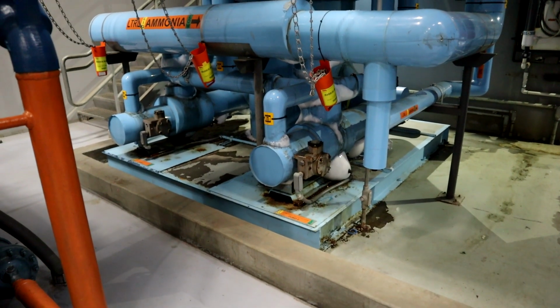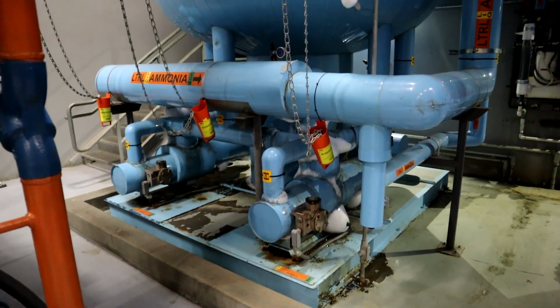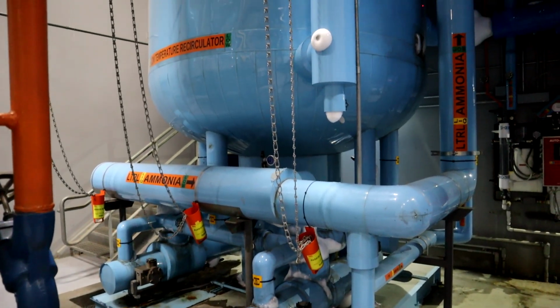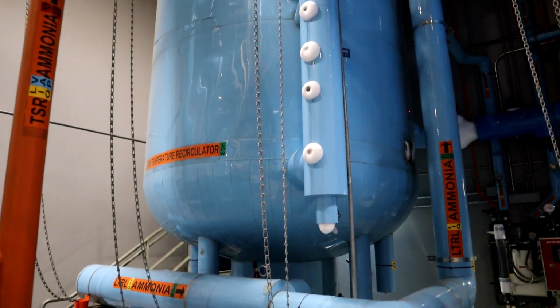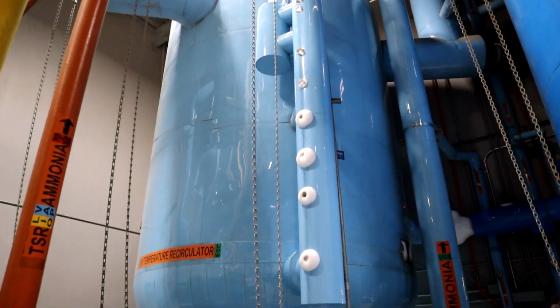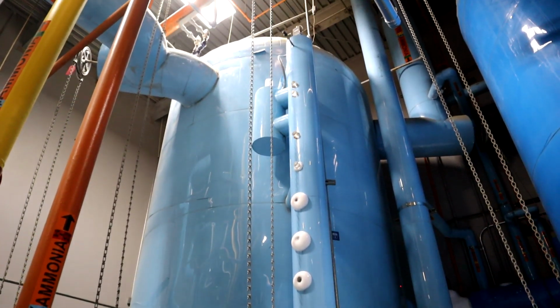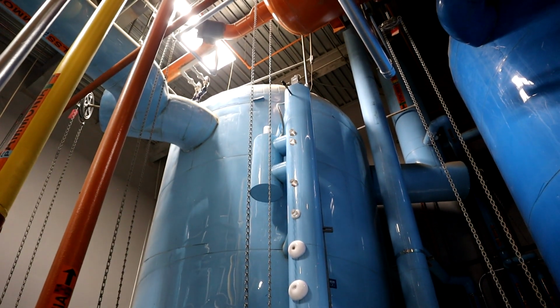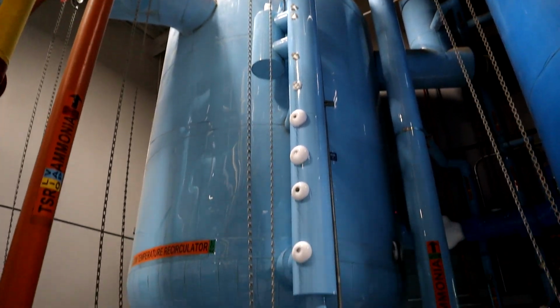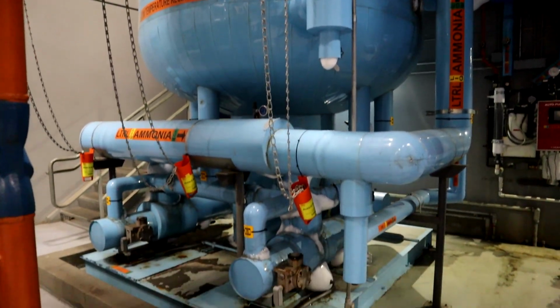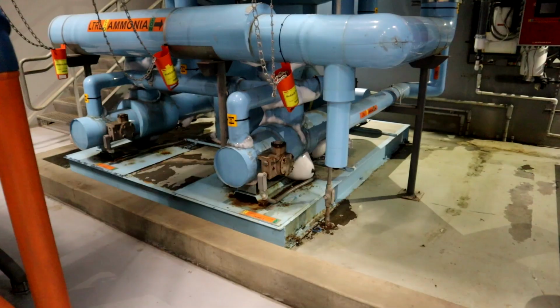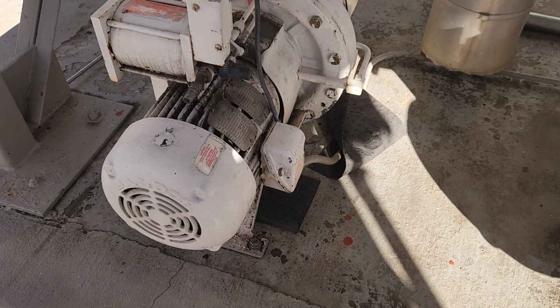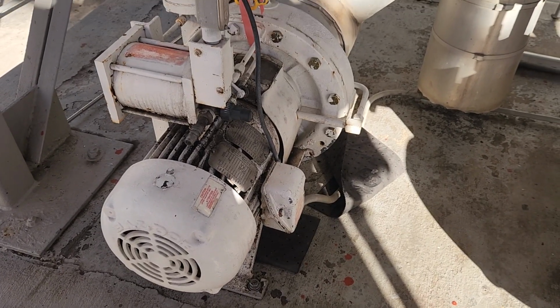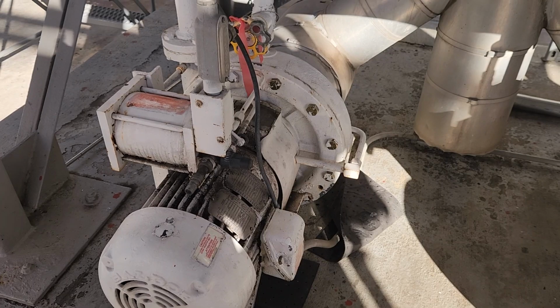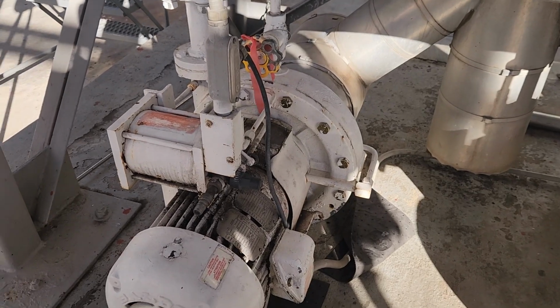Recirculators are often configured with a level probe that is interlocked with an electronic expansion valve to precisely control the level in the vessel. Because recirculators also provide vapor to compressors, they must also be configured with a high liquid level cutout that is wired to de-energize any compressor that receives vapor from the vessel. If the level drops too low in a recirculator, it can cause cavitation at the pump inlet, which is undesirable.